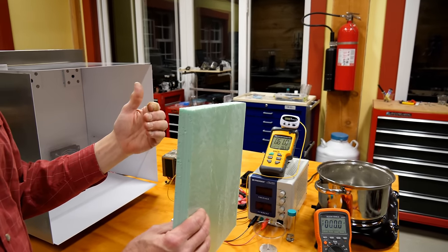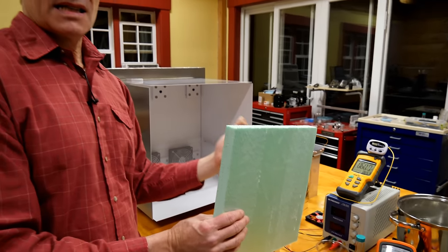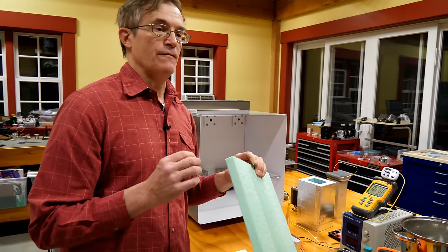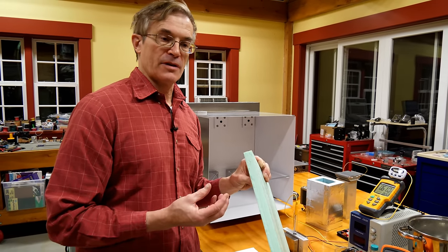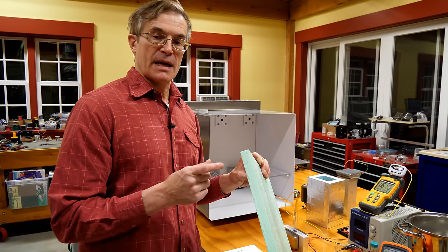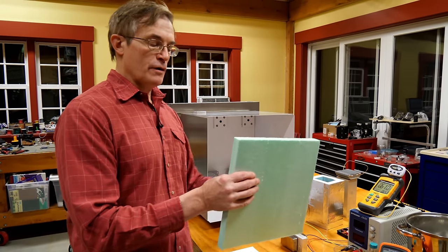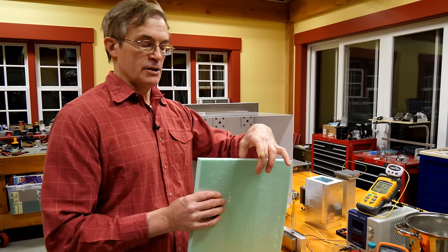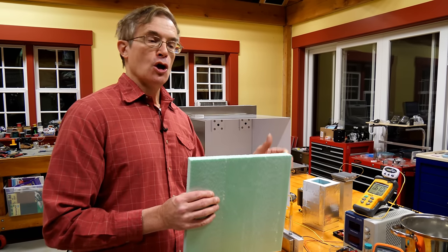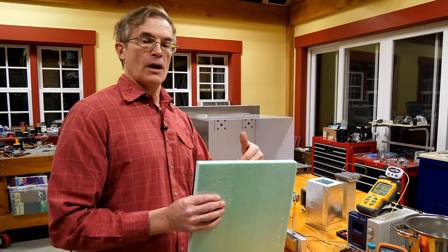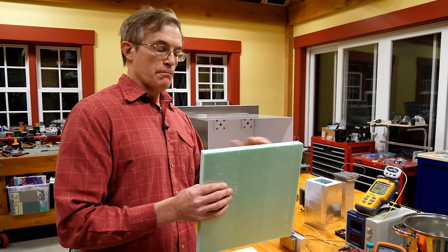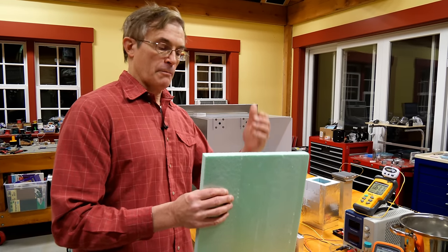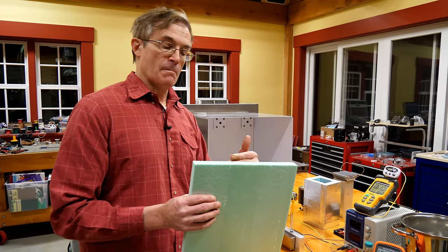Now, polyurethane has an R value of 6, and the thickest available panels of the polyurethane foam are 2 inches thick. As a consequence, a 1 foot square piece of polyurethane foam 2 inches thick will flow 1/12th of a BTU per hour per degree Fahrenheit temperature differential.